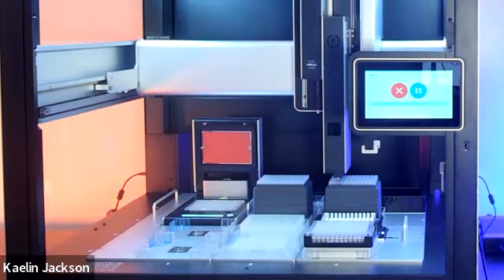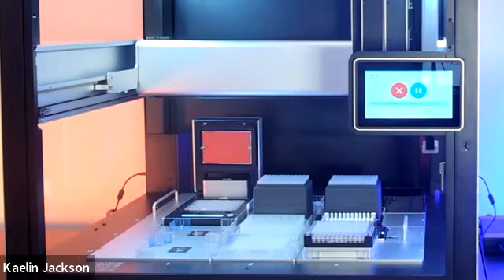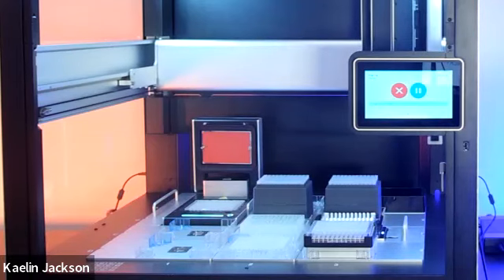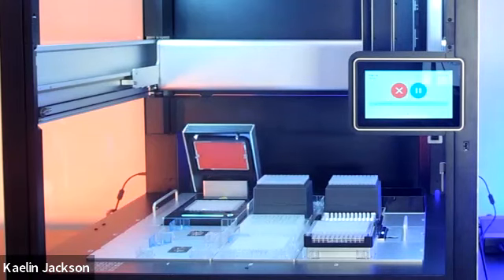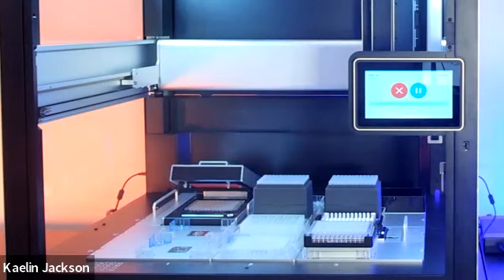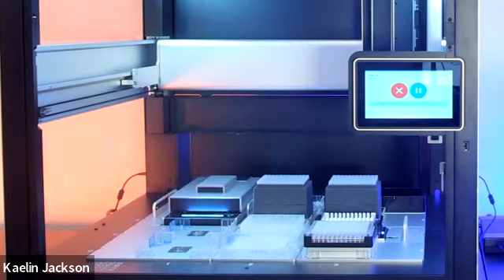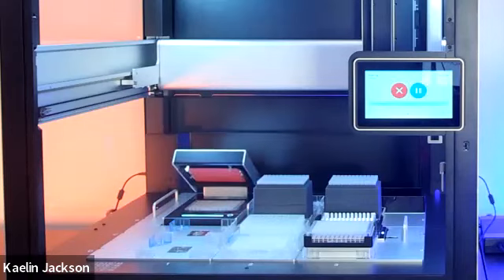The thermocycler can also automatically close and open the lid for cycling profiles or pipetting into the module. And before that happens, the pipette will home to safely accommodate the closing of the lid. The module also features a mechanically engaged lid, which ensures accurate pressure on the plate seal, ensuring no evaporation occurs. There's also a manual release in the event that you'd like to manually open up the lid. So here we'll automatically open.